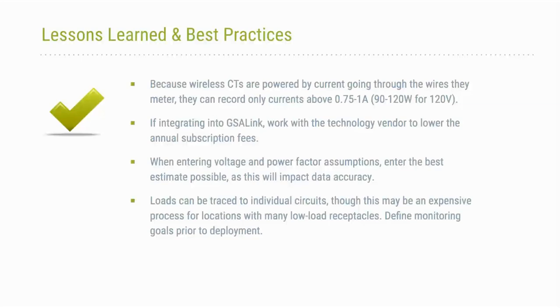Some lessons learned and best practices: as I mentioned before, these CTs are self-powered, so they require some current going through the wire, and this tends to fluctuate. According to the manufacturer's specs, they tend to be around 0.75 to 1 amp, but we've noticed they tend to be a little lower in the field.